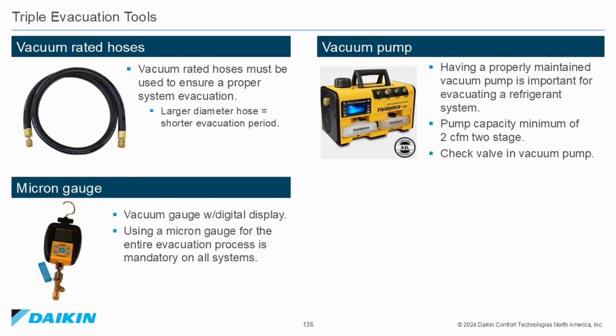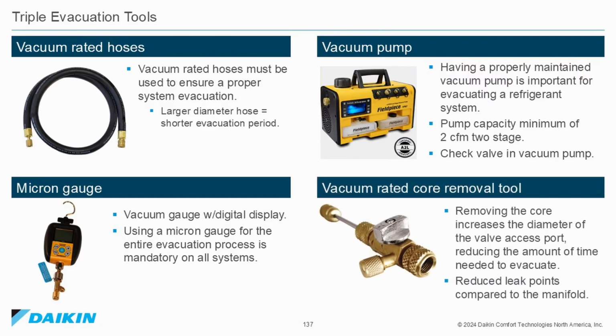Micron gauge is a vacuum gauge with a digital display. Using a micron gauge for the entire evacuation process is mandatory on all systems. And a vacuum-rated core removal tool. Removing the Schrader core increases the diameter of the valve access port, reducing the amount of time needed to evacuate. Gives you reduced leak points compared to the manifold.